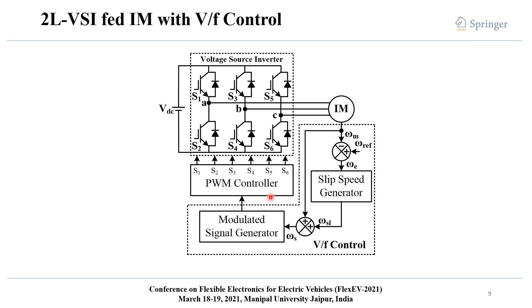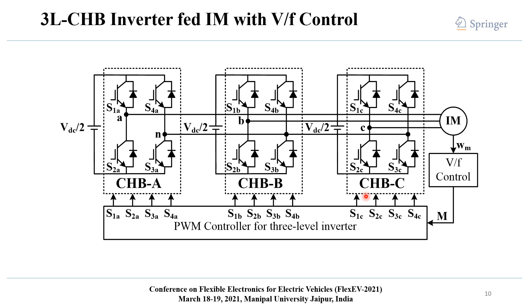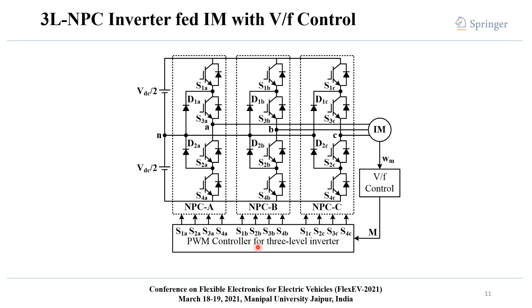This is a schematic diagram of a 3-level cascaded H-bridge inverter fed induction motor drive with V/F control. Using the same V/F control as before, a modulated signal is generated, and based on this, a PWM controller for the 3-level inverter generates the switching sequence for each leg of the cascaded H-bridge inverter. This is the schematic diagram of a 3-level neutral point clamped inverter fed induction motor drive with V/F control, operated using the same control scheme as the 3-level CHB inverter.